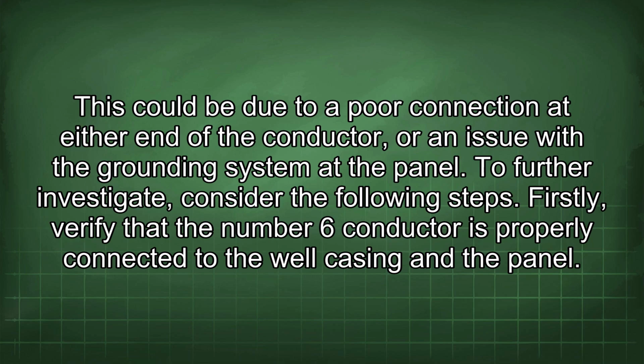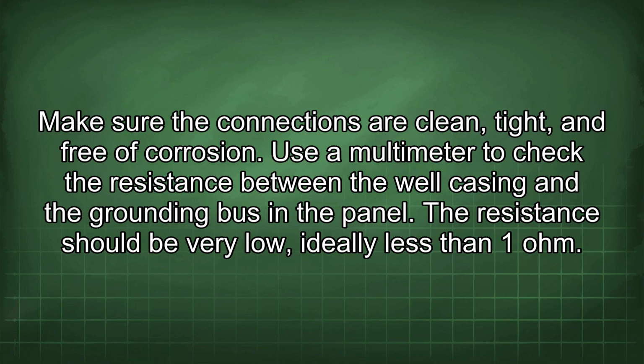To further investigate, consider the following steps. Firstly, verify that the number 6 conductor is properly connected to the well casing and the panel. Make sure the connections are clean, tight, and free of corrosion. Use a multimeter to check the resistance between the well casing and the grounding bus in the panel. The resistance should be very low, ideally less than 1 ohm.